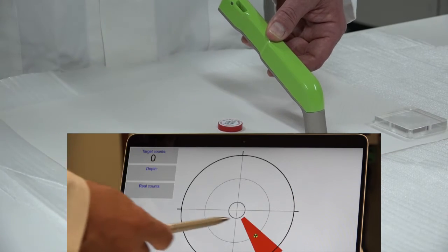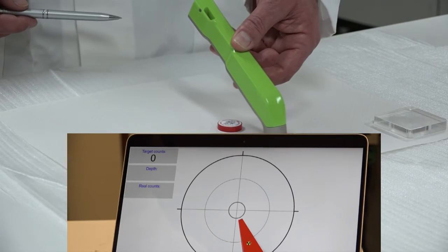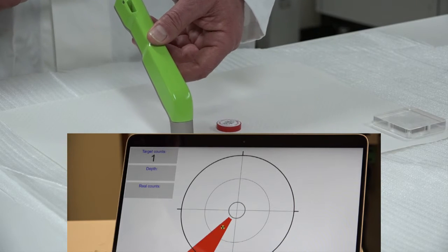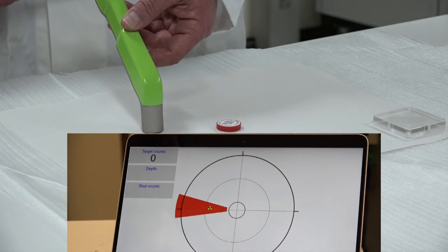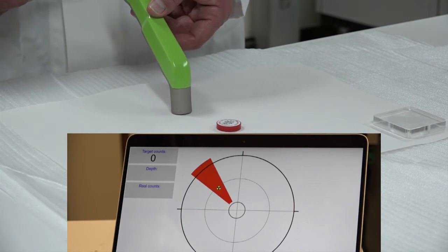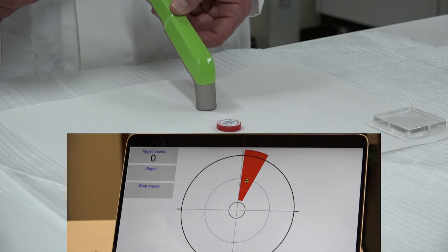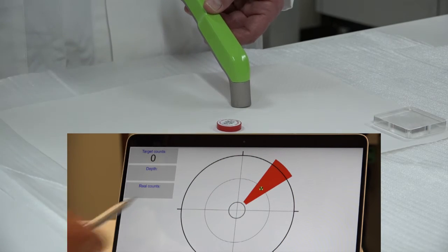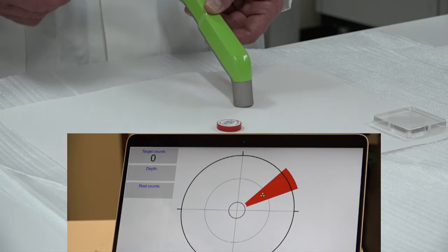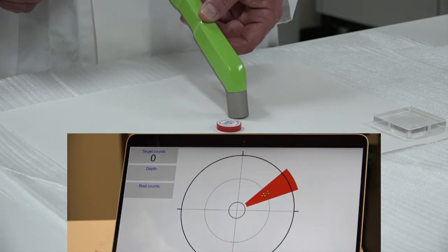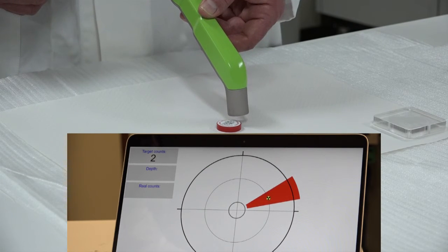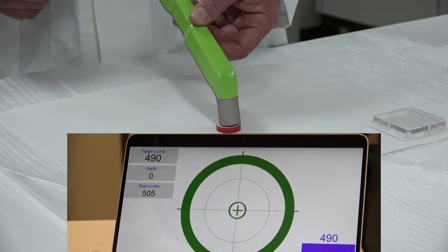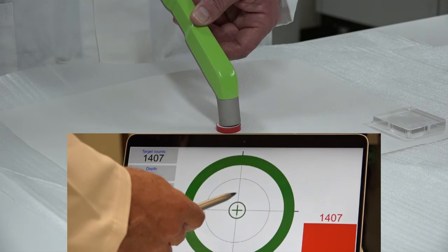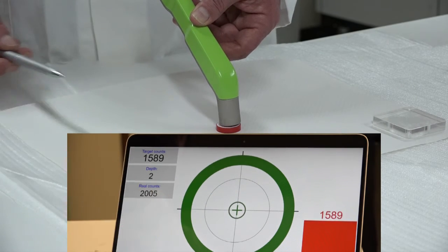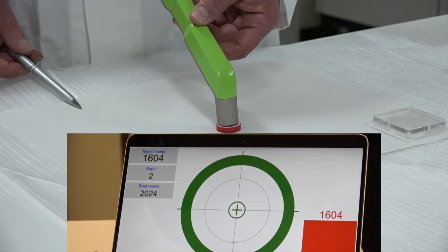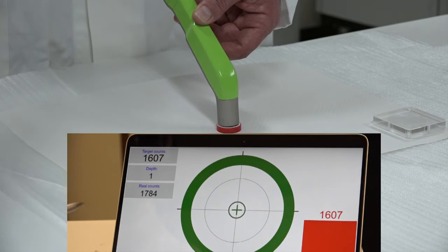As I move the probe around the radiation source, the direction instructions I am given by the navigator will simultaneously change. Having clearly understood the exact position of our source, and by moving the probe up to it, we will be given the lock-on target signal. We are concurrently given the exact position of the probe relative to the source, as well as the exact distance between its surface and that of the isotope.